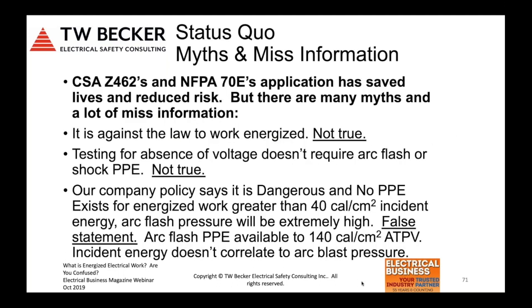So these are some of the myths and misinformation that relate to our discussion of what is energized electrical work, and are you confused? These are statements, or some of the things that I've come across in the last 5 to 10 years. It's against the law to work energized. That's not true. Again, Rule 2-304 is being miscommunicated from the Canadian Electrical Code here in Canada, and even the regulations. I gave you some examples. It's not against the law to do energized work. The government would just want the arc flash and shock hazards identified and risk control methods implemented. Testing for absence of voltage doesn't require arc flash or shock PPE. That's not true. Until we achieve absence, you assume the voltage is there, and arc flash and shock hazards can exist.